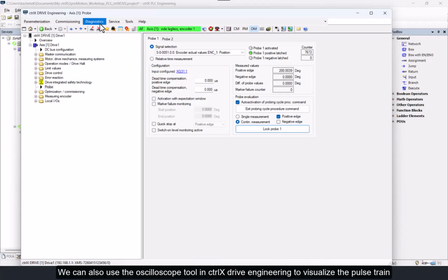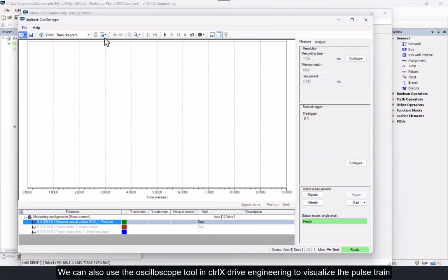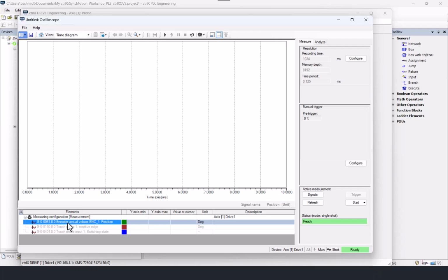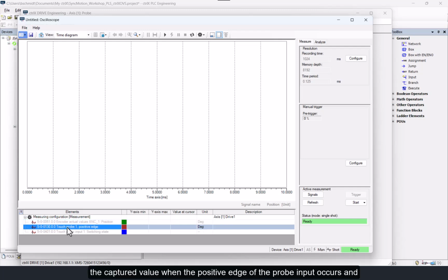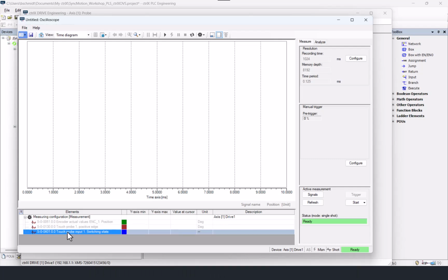We can also use the Oscilloscope tool in ctrlX Drive Engineering to visualize the pulse train from the PLS output and check the correlation with the position feedback. I have the oscilloscope configured to capture the actual position value at any moment in time, the captured value when the positive edge of the probe input occurs, and the state of the probe input, 1 being on and 0 being off.